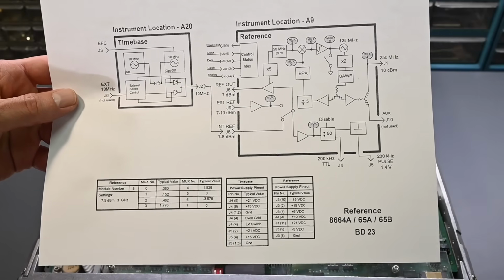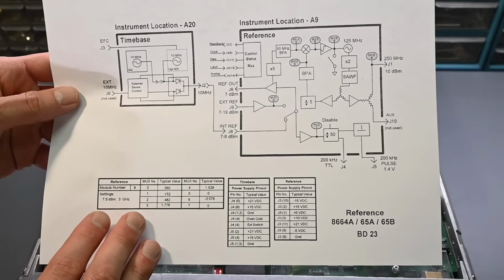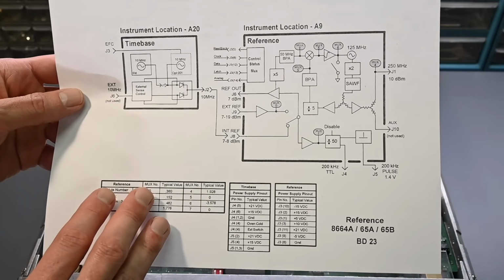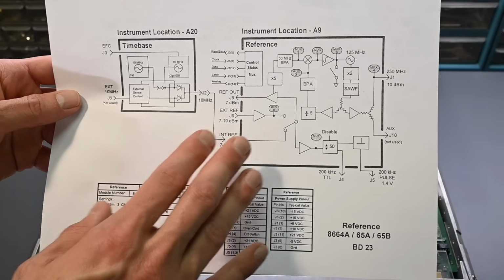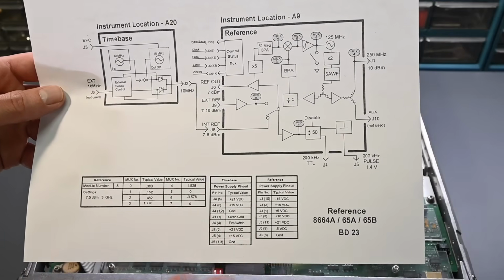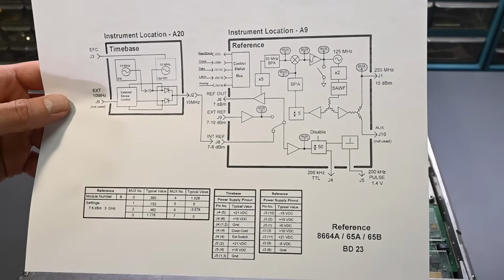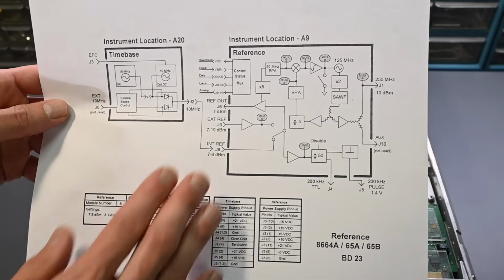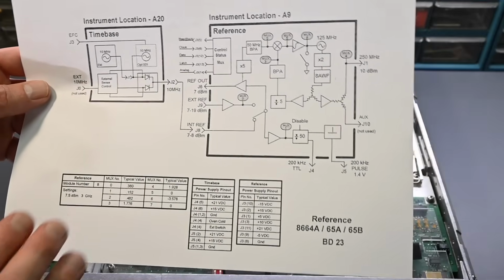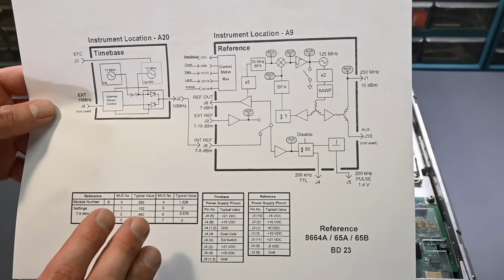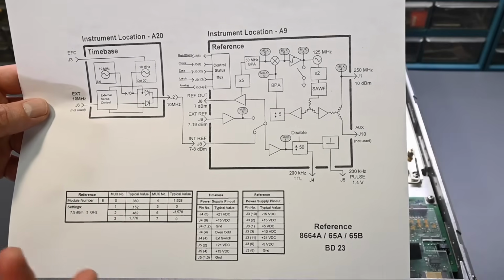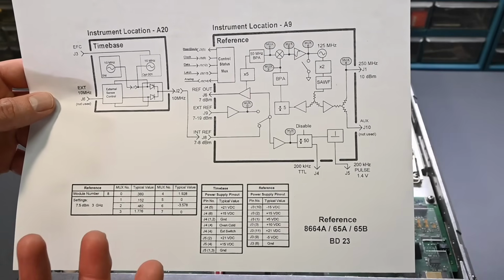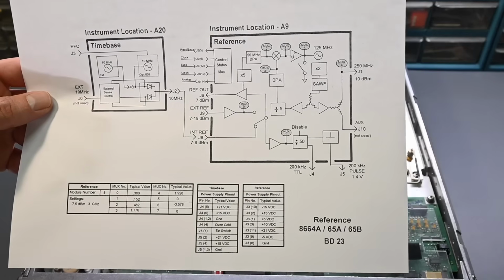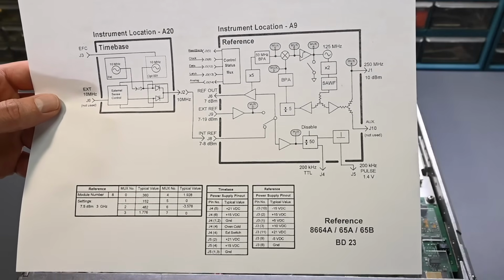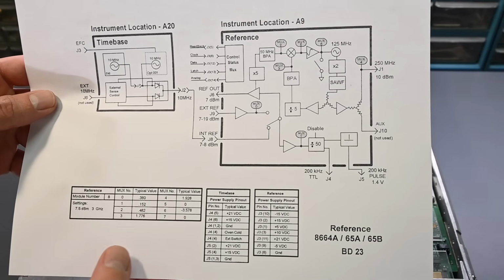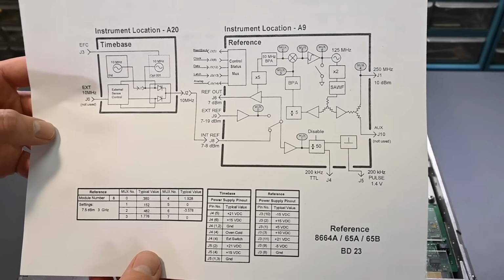So on the Keysight website, you can download the user manual and the service manual for this instrument, and the service manual has block diagrams and all the service troubleshooting and so forth, the built-in self-tests, the calibration, everything like that. So very useful. And there are a lot of block diagrams, but there are no actual schematics. And the schematics would have been in what's known as a clip. And the clip stood for Component Level Information Packet. And it would have been hundreds of pages long. And unfortunately, those aren't available. I've never been able to locate one for this instrument. So yeah, I don't think they were ever released.